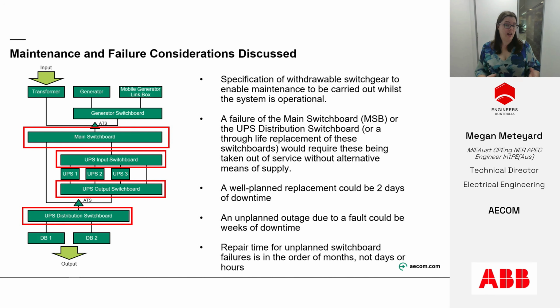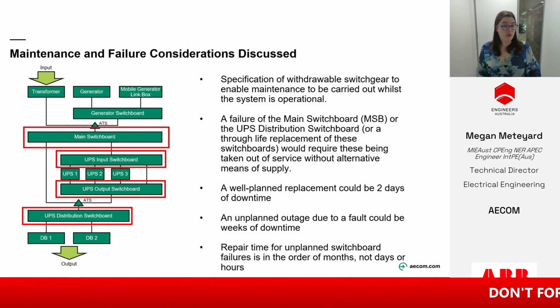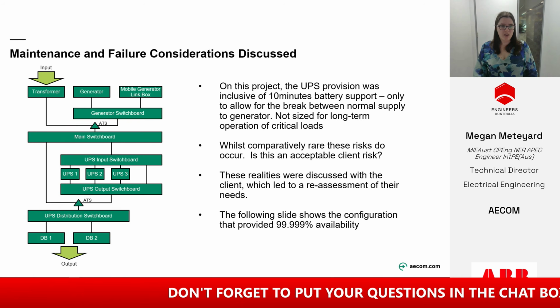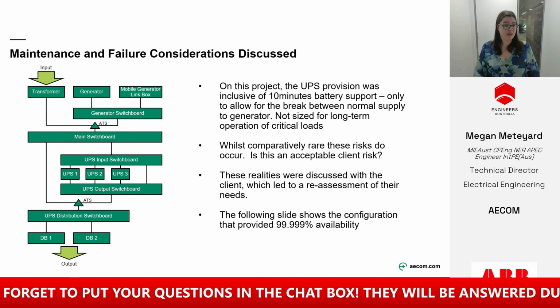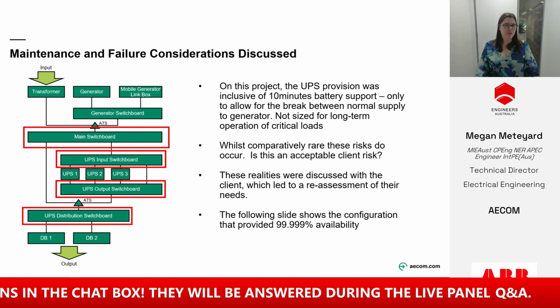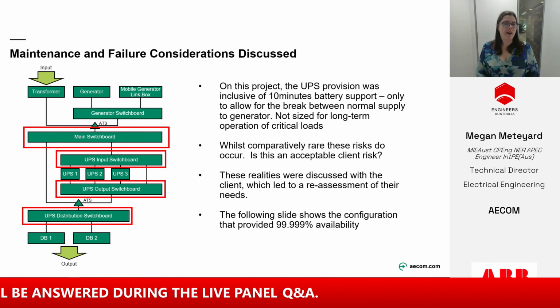So in terms of a well-planned replacement, that could be, say, 2 days of downtime. But an unplanned outage due to a fault could be weeks, or an unplanned failure of a switchboard could be in the order of months, not days or hours. So again, on this project, the UPS provision that was in the network was 10 minutes of battery support. So it was really just designed to allow for that no break between the mains fail and the generators kicking in. It wasn't so much for long-term operation.